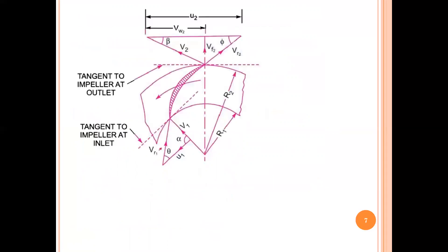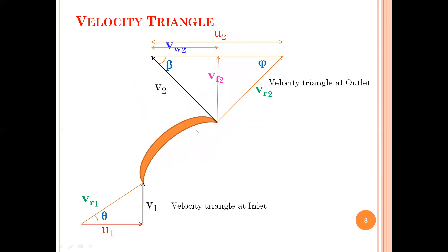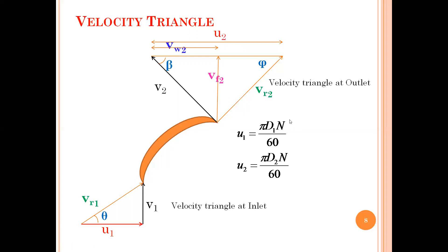A small introduction to the velocity triangle: this is how your backward curved radial vanes look. The water enters radially inside, so the alpha angle is 90 degrees. At inlet, we get: Vr1 (relative velocity), θ (blade angle), U1 (peripheral velocity), and V1 (absolute velocity). Your absolute velocity and relative velocity are in two different directions. U1 and U2 are given by πDN/60, where N is the speed of the impeller, D1 is the diameter at inlet, and D2 is the diameter at outlet. The work done calculation will be done in the next class. Thank you.